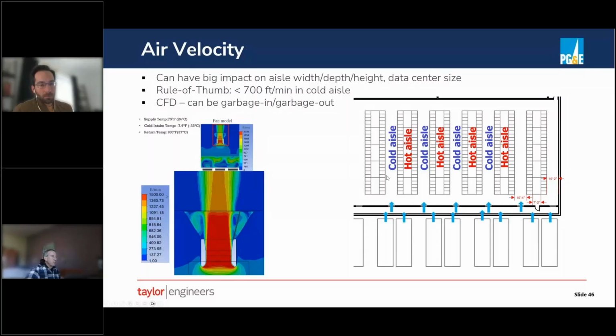What can happen is that if the velocity is too high, the Bernoulli effect, if you will, can create a zone of negative pressure in front of that server. The air rushing past it will basically suck air backwards through that server, and so the server won't be able to properly cool itself. Its fan won't be able to pull enough air from the cold aisle to keep it satisfied. And I've seen people use CFD, computational fluid dynamics modeling, to validate data center designs that had things like 2,000 feet per minute velocity.